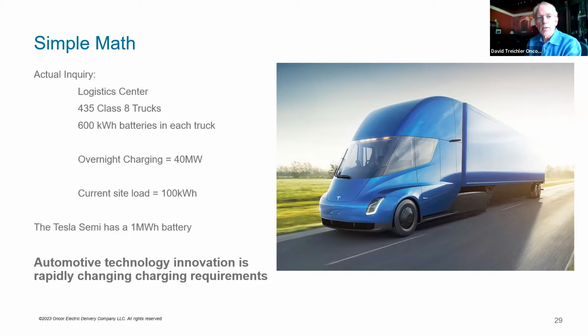The 600 kilowatt hour battery is what's in the current Daimler Freightliner trucks, the Volvos, Peterbilts, and some others. But the Tesla Semi pictured here has a 1 megawatt hour battery and uses a 1.5 megawatt charger. I belong to a bunch of the standards committees around charging, and at a committee meeting this last week, they were talking about the charging standard they're putting in place for mining trucks and ferry vehicles. That standard runs from 10 to 40 megawatts with a charger.